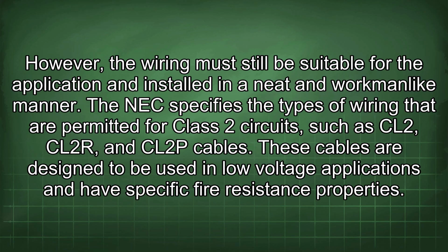However, the wiring must still be suitable for the application and installed in a neat and workmanlike manner. The NEC specifies the types of wiring that are permitted for Class 2 circuits, such as CL2, CL2R, and CL2P cables. These cables are designed to be used in low-voltage applications and have specific fire resistance properties.